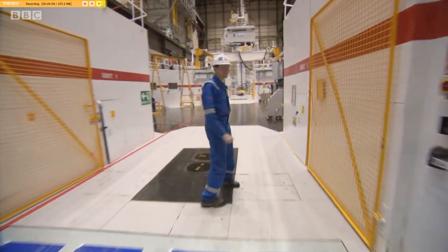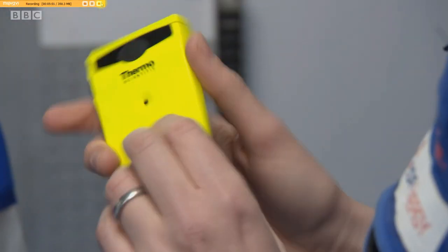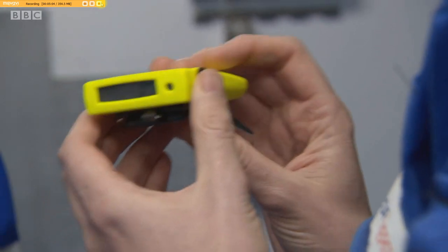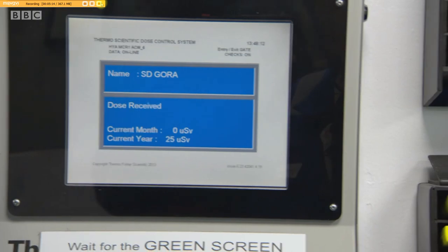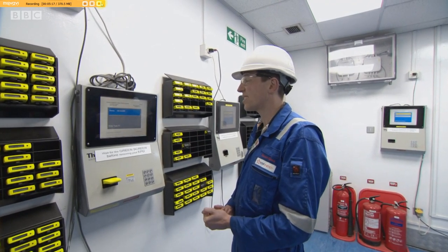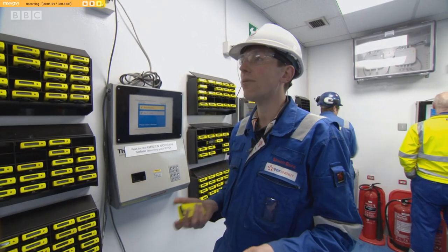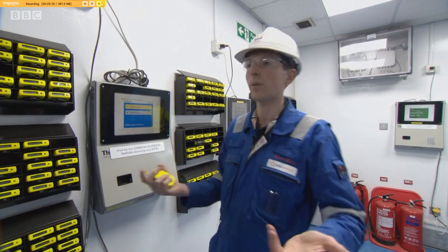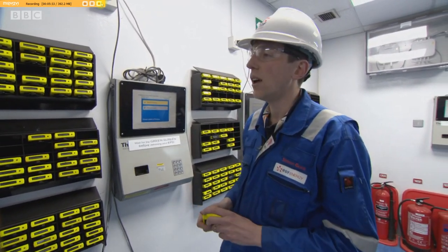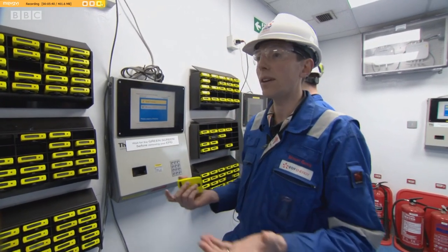Levels are constantly monitored, and it's Simon Gore's job to make sure strict guidelines are maintained. We have electronic personal dose meters. These will record the dose that people are getting inside the reactor building, and they'll also alarm if anybody goes in an area where the dose rates are higher than expected. I've had zero microsieverts this month, and over the course of the year, 25 microsieverts — which is really comparable to maybe a chest X-ray. On a yearly basis, the average person gets about 2,600 microsieverts just living their everyday life, from cosmic radiation and natural sources. Our typical doses here to an average worker are maybe 10 to 20 microsieverts.